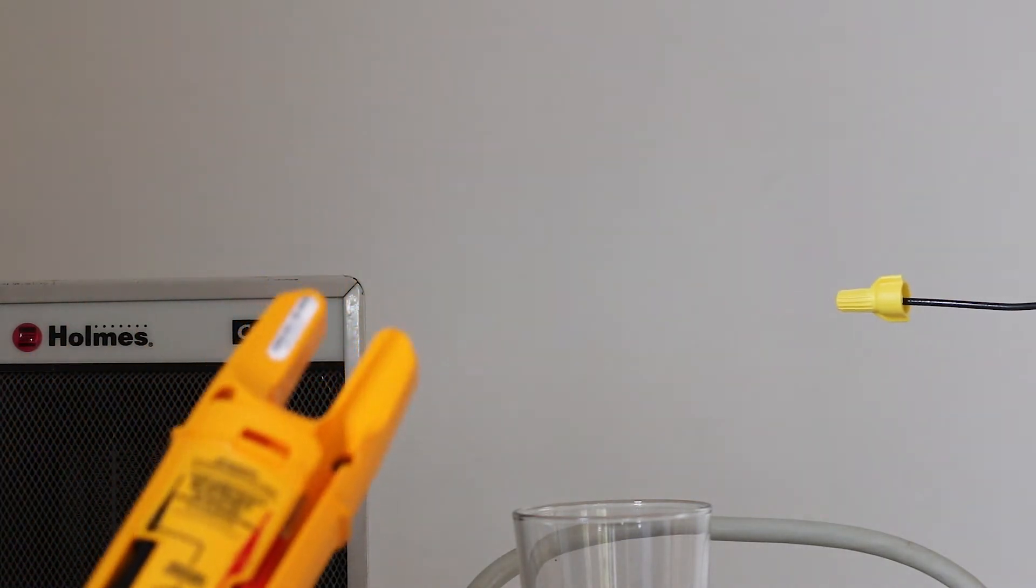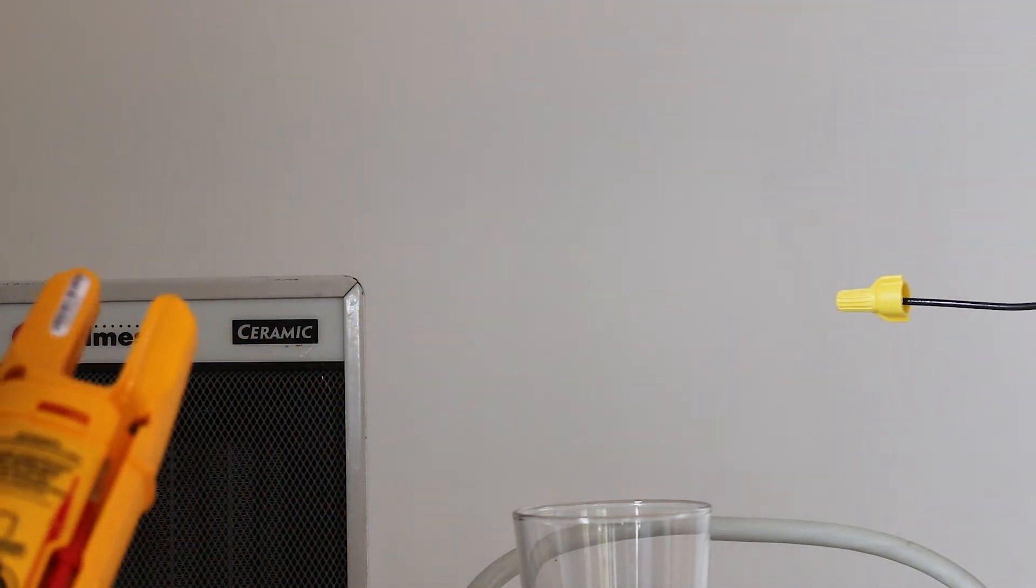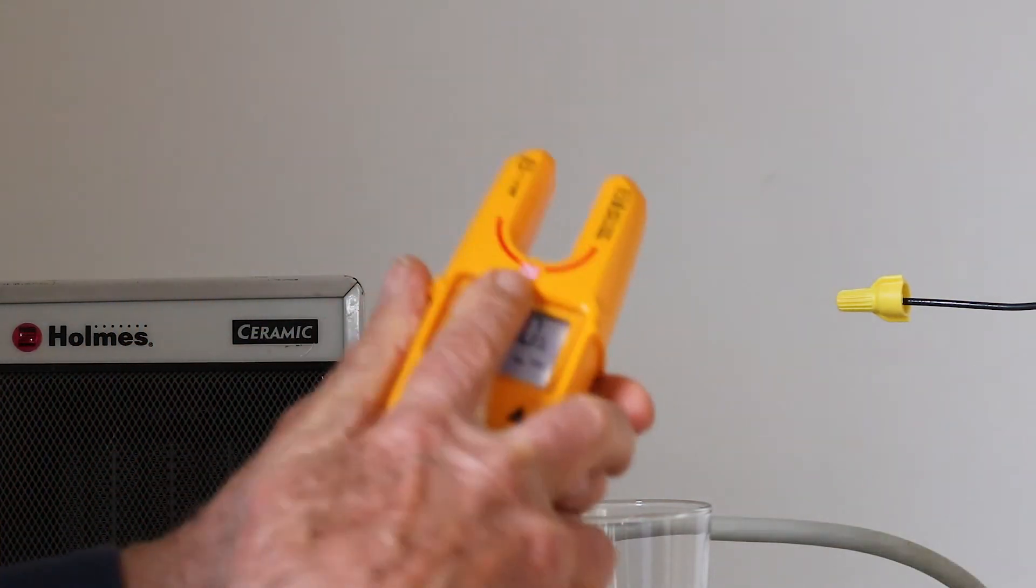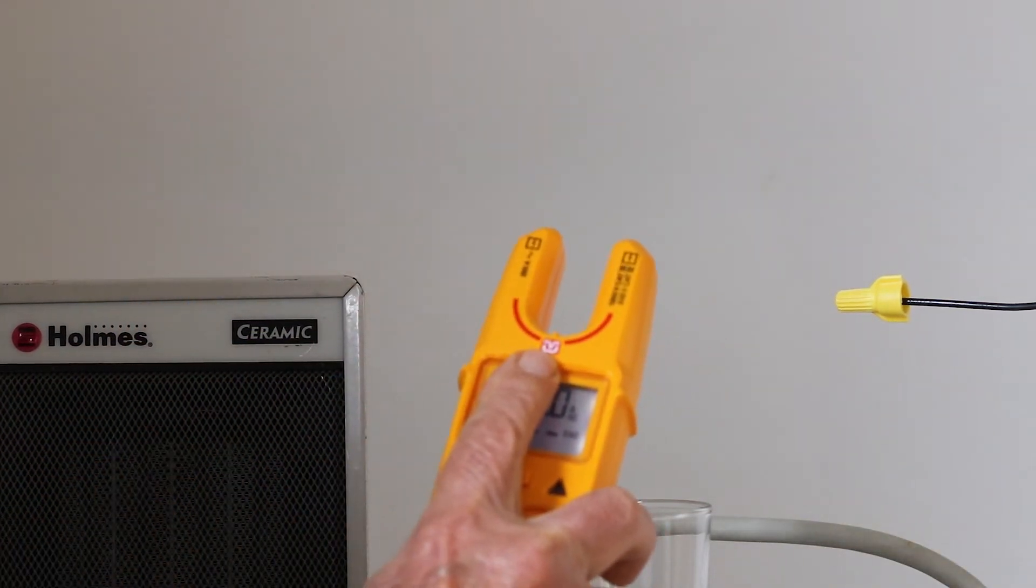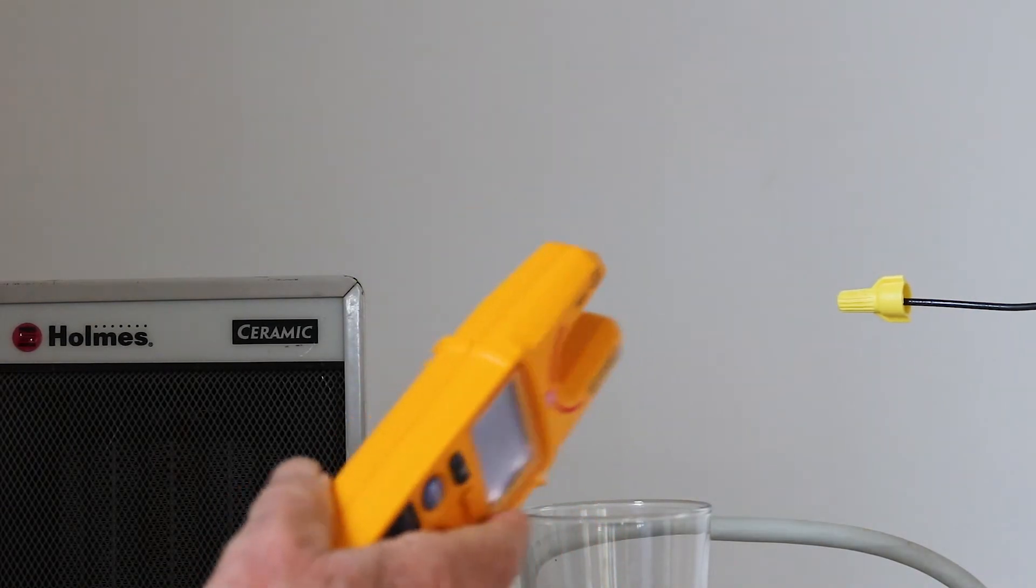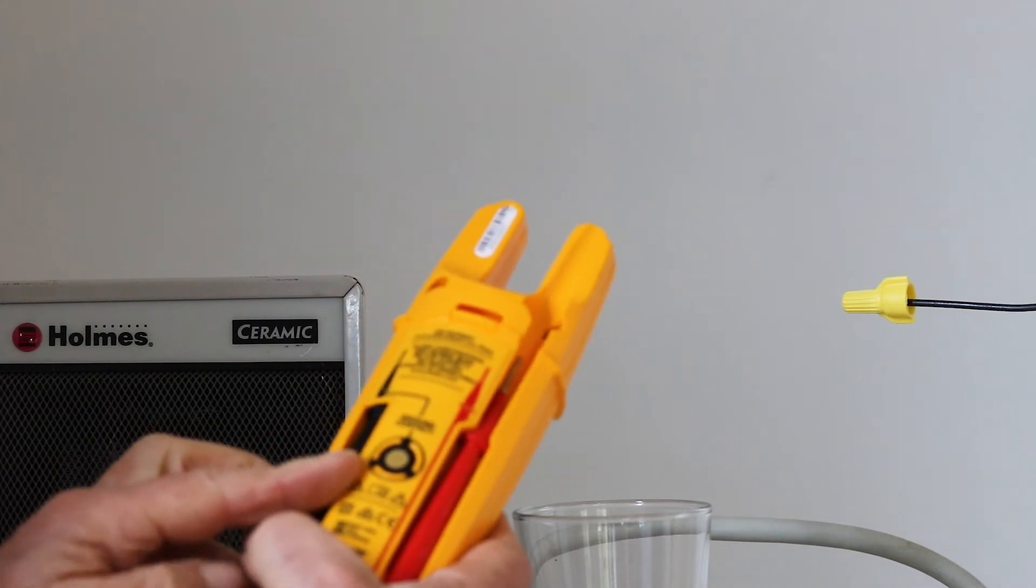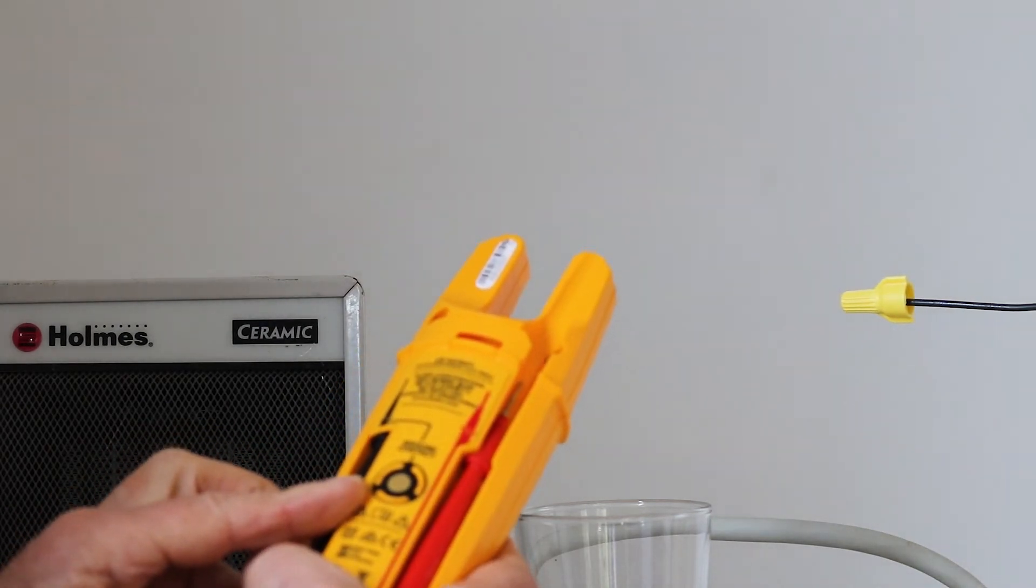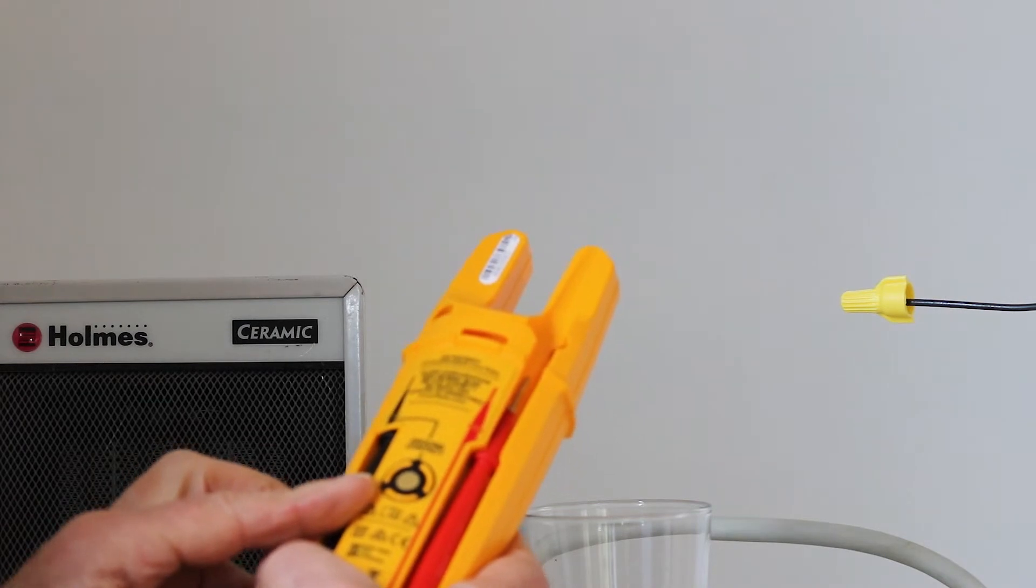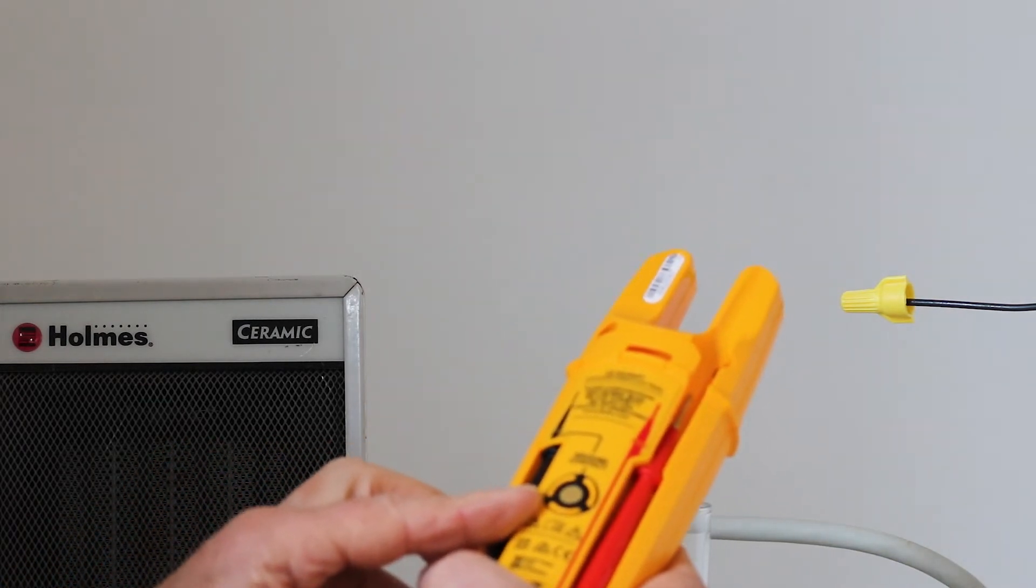To take a reading, the wire has to be set against the bottom center of the jaws. Then, while taking a reading, place your finger against the spot indicated on the back to capacitively provide the ground potential so that the meter can sense the electrostatic field.